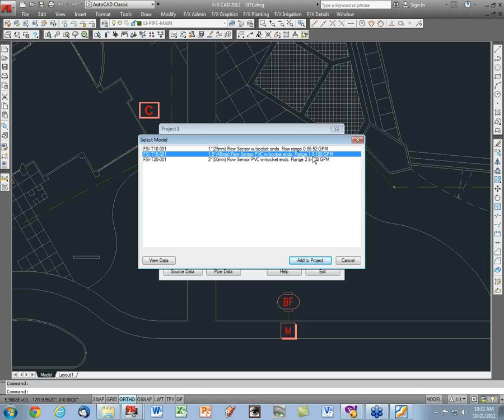It's very insignificant as a loss, even though it is a much smaller pipe size. So don't let that fool you, the fact that you could have a mainline pipe of 2.5 inches and this flow sensor sized 1 or even 2 pipe diameters less than that. Very easily done on that, and this would be 2 if that were the case.